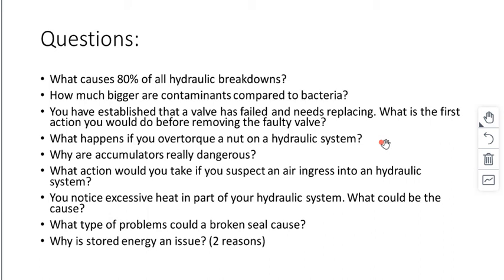Why is stored energy an issue? And we're looking for two reasons. Okay, so obviously the first reason is stored energy can be released at times when we don't want it to be released. Yeah. So we need to be aware of that, of accumulators. So if we depressurize an hydraulic system, the accumulator valve needs to be in the open position, yeah. So for the oil to leak out of the accumulator back into tank, so that's very, very important. And that's one. And the other one is just health and safety as well. So if you take it off, and I mentioned this umpteen times, I'm going to mention it again because it's important. If you take it off, it could cause a huge, huge amount of problems.